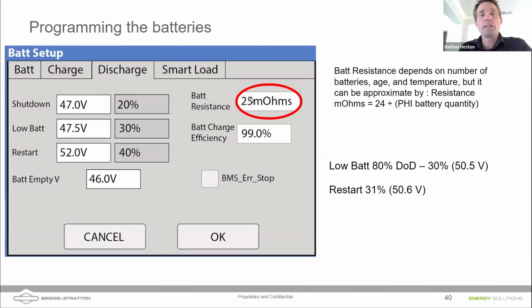The reason for that is when you're drawing at heavy loads, you're actually losing some voltage across the resistance of the batteries. And the inverter is smart enough to calculate that voltage drop based on this resistance. I do point out it is a bit dependent on temperature. So this is not a dynamic value, but it certainly helps take into consideration some of the drops in the batteries. I'll take a second and jump into the questions.